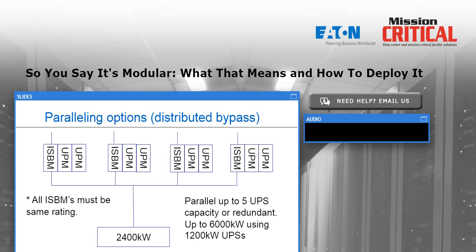Do UPS modules share a common battery in a typical system? In a modular UPS system, more often than not, they will share a common battery. So the question likely is, is that a reliability issue? And we recommend, as do our other folks in the business, to have a multi-string battery. So a problem or an integrity problem in a single battery string would not remove the backup capability of the entire UPS system. So a multi-string battery is better than one large single string of batteries.